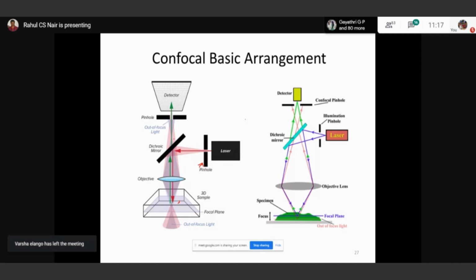Okay. So the emitted light from the specimen falls onto the detector. Here you can see there are two emitted light spectra, the in-focus light and the out-of-focus light. With this pinhole, the out-of-focus light is completely obstructed, and only in-focus light enters the detector, and that is the reason for the crisp image.